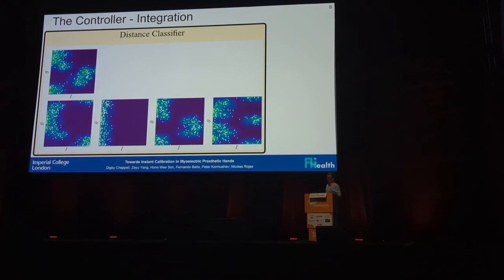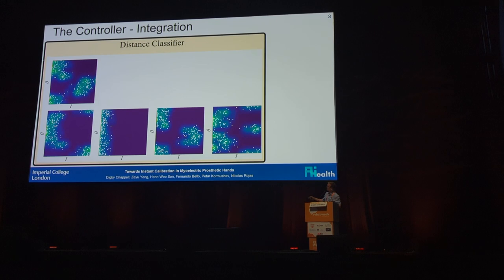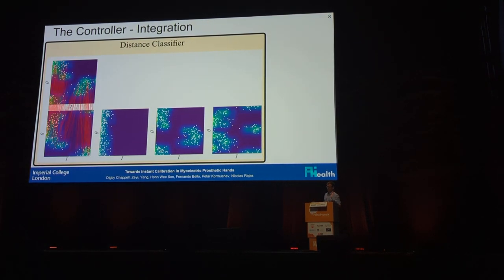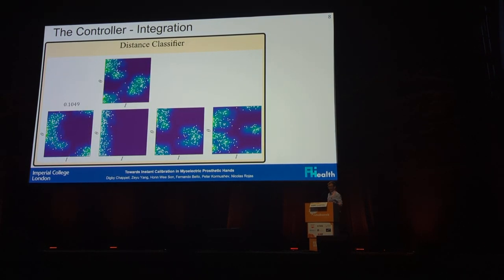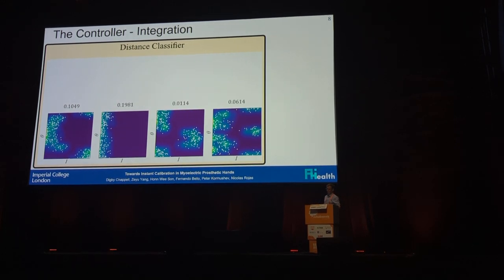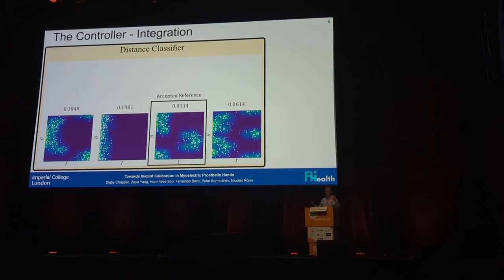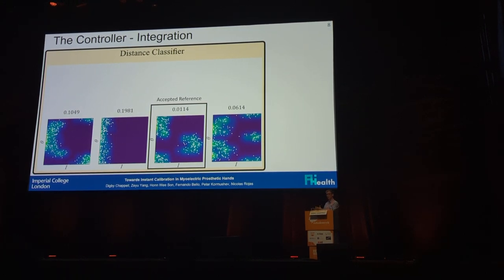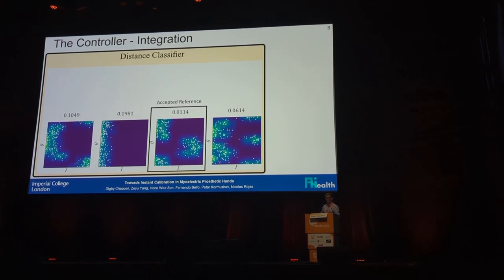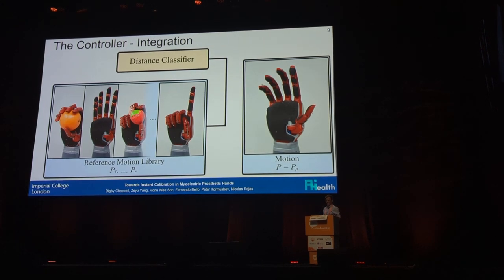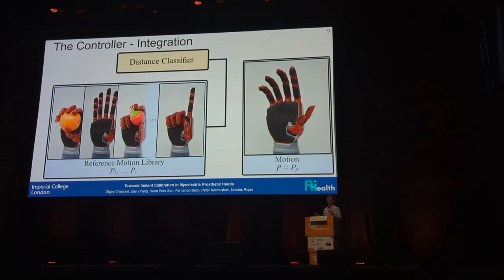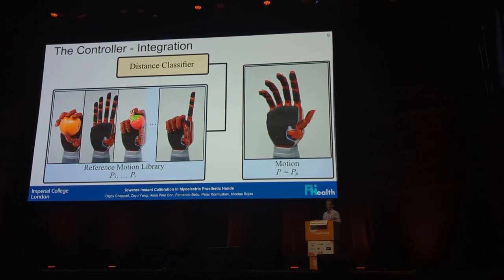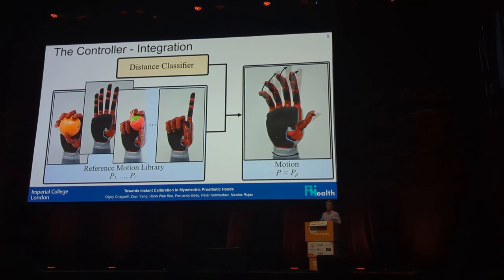The way we integrate this into a prosthetic hand controller is: we have our live EMG distribution, we have a series of references, we compute the distance, repeat that for all of them, then select the one that's closest and falls below our threshold — basically saying your EMG is close enough to this reference, so you must be wanting to do that motion. Whatever reference muscle activity you recorded corresponds to a reference motion, and we select that as what we want to do.